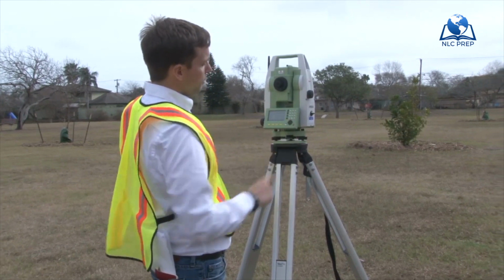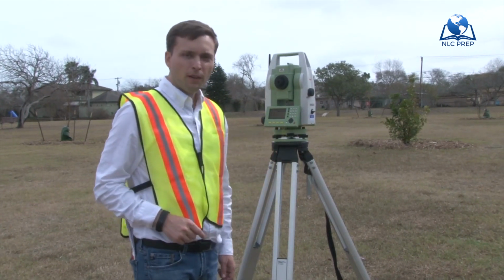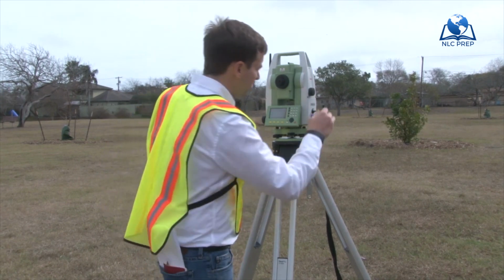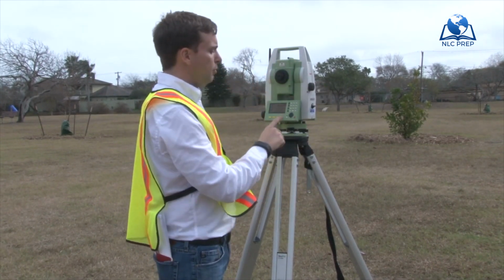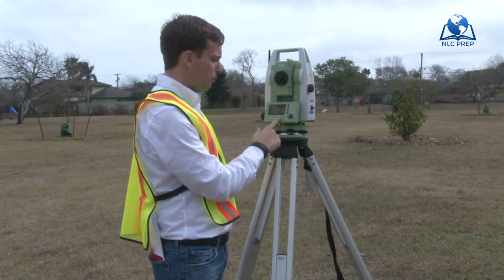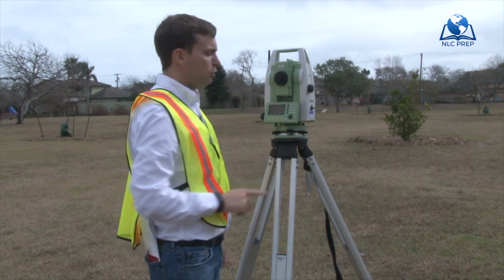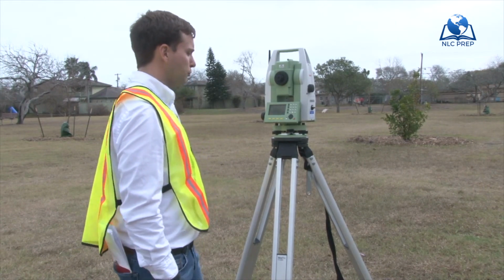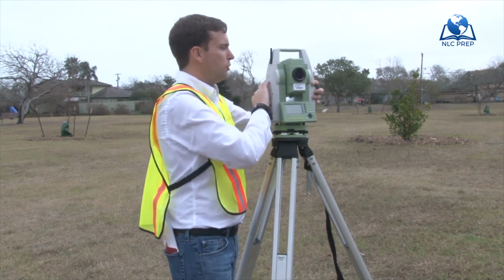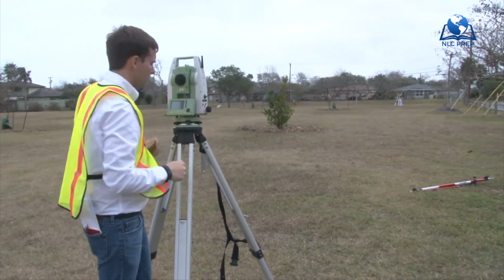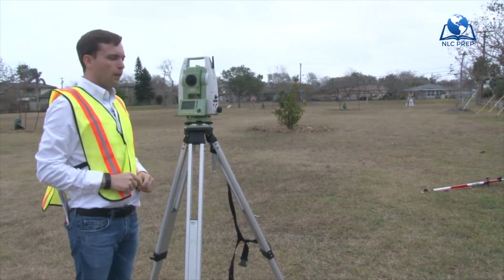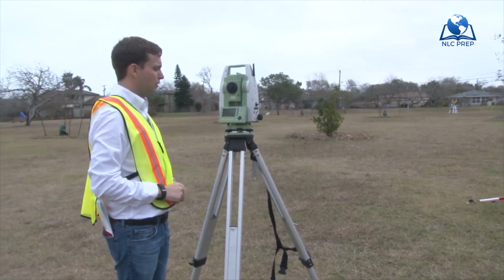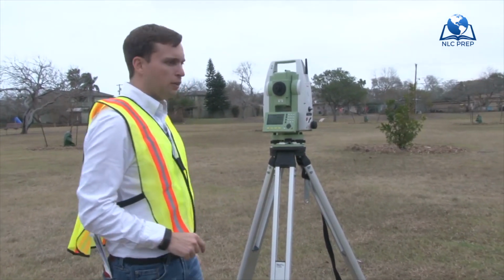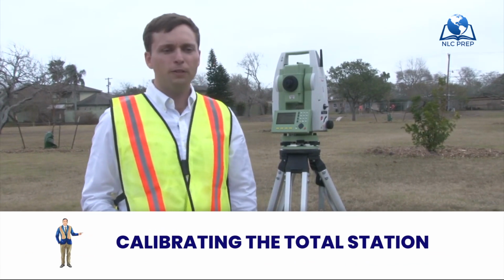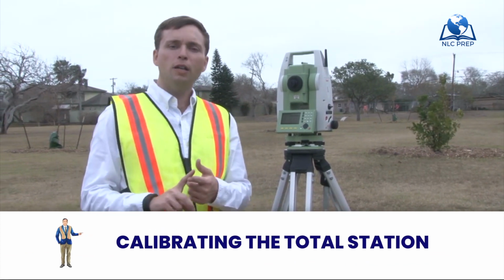I'll click Side, and it's going to say Vertical Index. Same procedure. Aim your instrument approximately plumb at least 100 meters. Continue, and then Store. It'll take some measurements. And now it's going to prompt us again to change the face. And again, I'll hit Store. It'll take some measurements. Set. And look at that, we were only off 3 seconds. Perfect. And that's it. Horizontal collimation, vertical index, and we're finished.